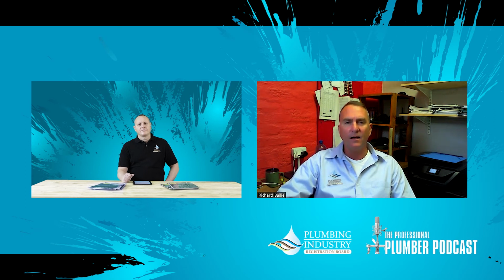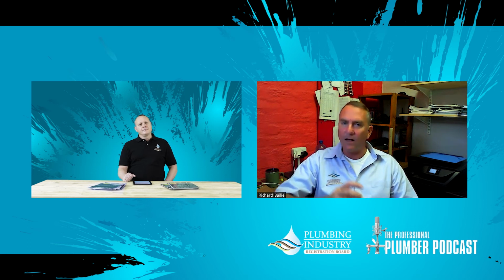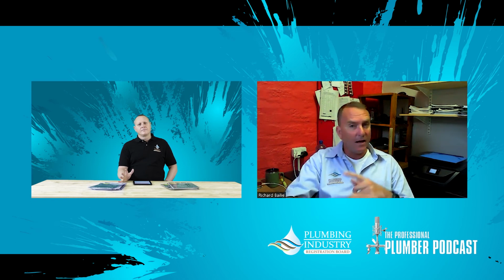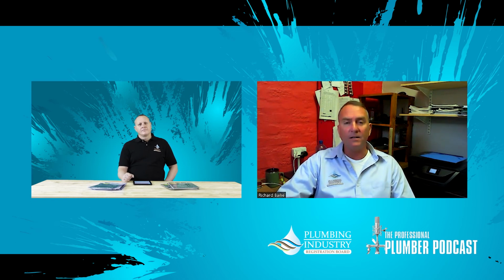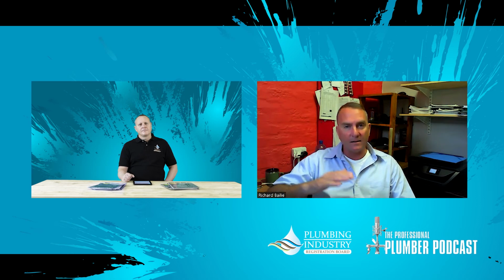geyser. And I just want to reiterate again, for understanding and clarity, a heat pump relies on the circulation of the water through itself and multiple volumes of the geyser's volume through a heating cycle. It could be 5, 6, 7 volumes of the geyser circulating multiple times through the heat pump in order to bring that volume of water up to temperature.